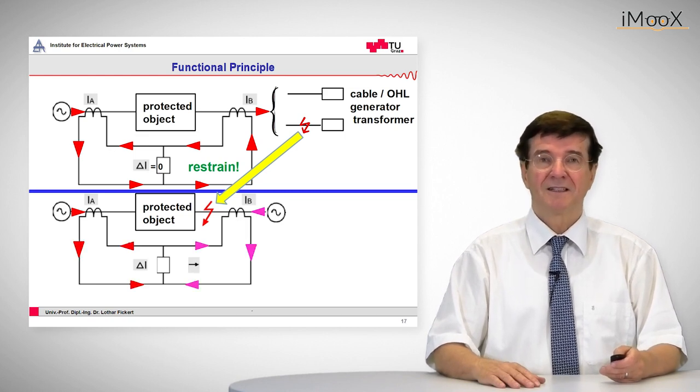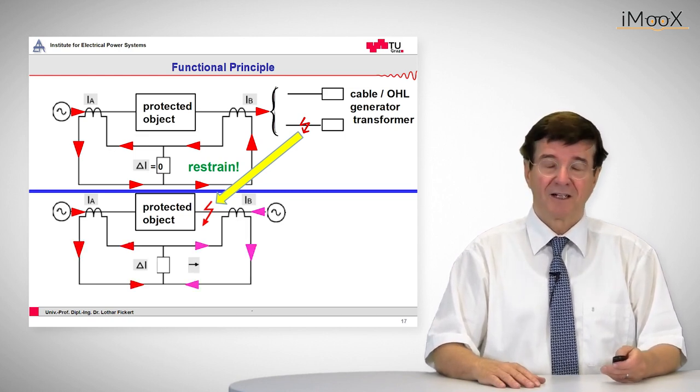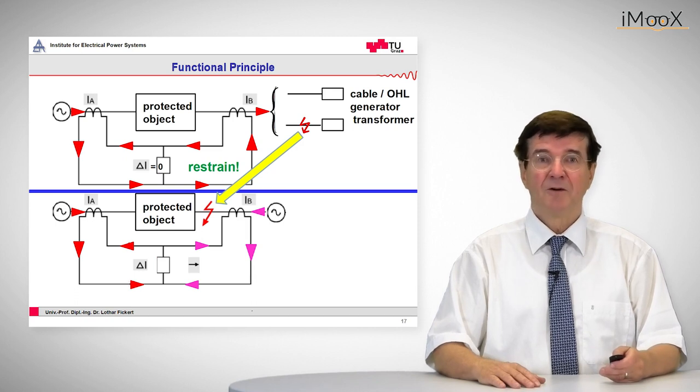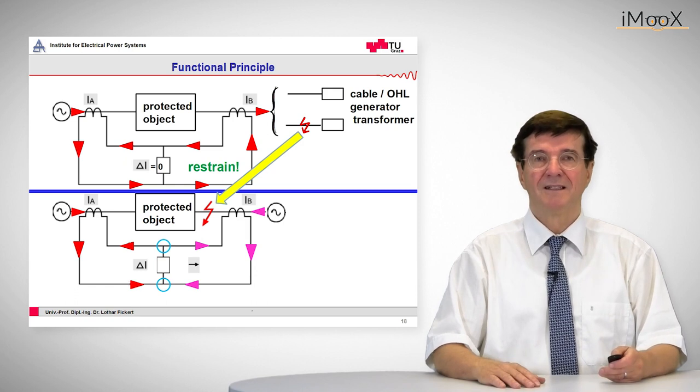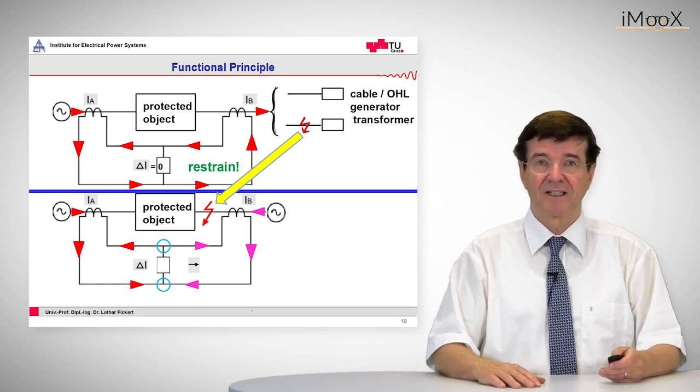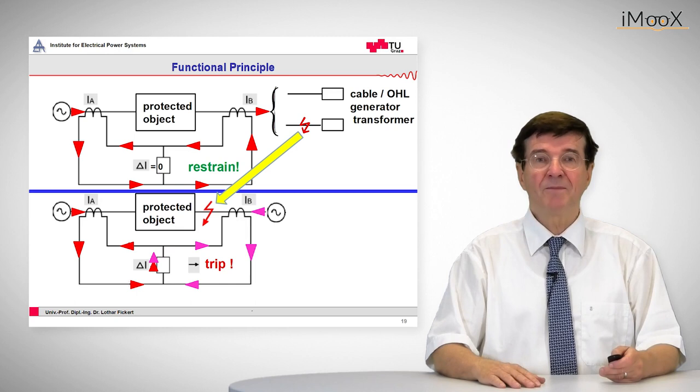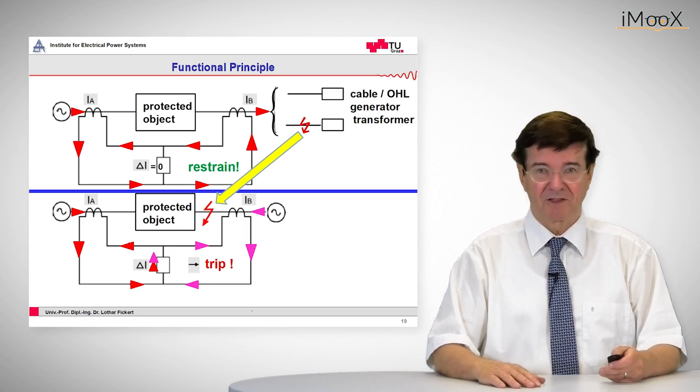And these generate accordingly currents on the secondary side which have opposed polarity. So when these meet at the sensing point of the differential current sensing unit, they add up and we have a trip condition.